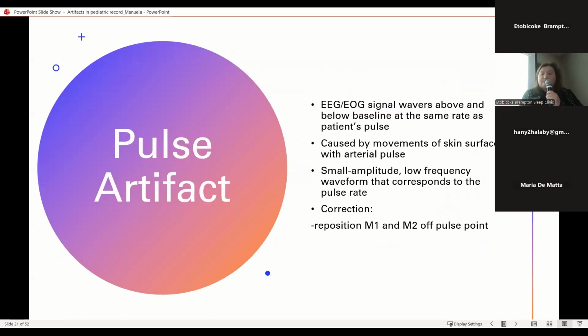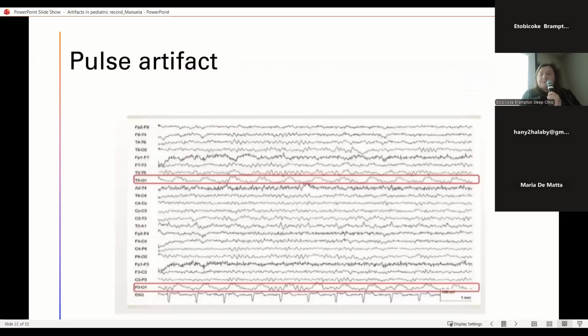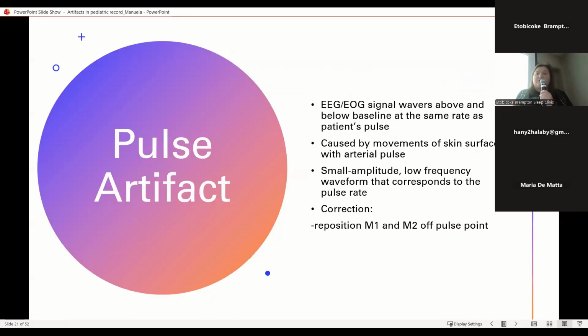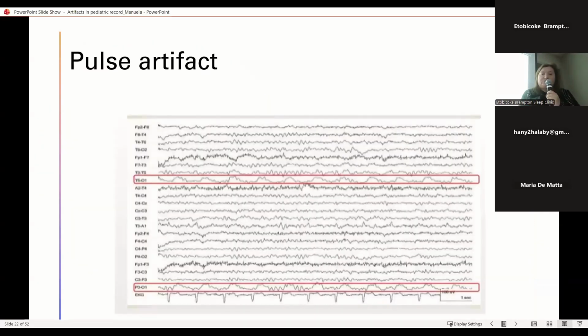Pulse artifact. It looks like this. EEG and EOG signal wavers above and below baseline at the same rate as the patient's pulse, caused by movement of the skin surface with the arterial pulse. Small amplitude, low frequency waveform that corresponds to the pulse rate. Correction: reposition M1 and M2 off the pulse point. So it's somewhere M1 or M2 is on a vein, next to a vein or an artery. And that's why it happens.